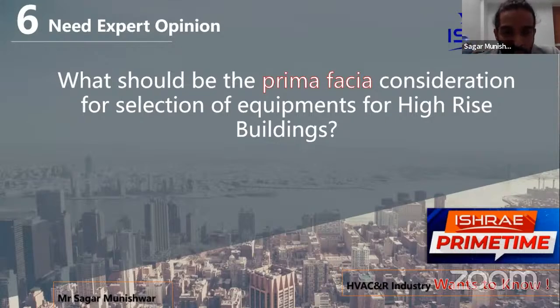Yes. When it comes to the other firefighting systems, the automatic sprinkler system and the hydrant system, yes. Of course, the sprinkler system per se can take only 12 bar pressure. If your system goes above 12 bar pressure, you can have an orifice plate or a pressure restricting device, which can control the pressure across your line. For the hydrant system, again, no issue at all. You just have to maintain 4.5 bar pressure at the outlet of the hydrant valve, which is again possible by introducing an orifice plate.